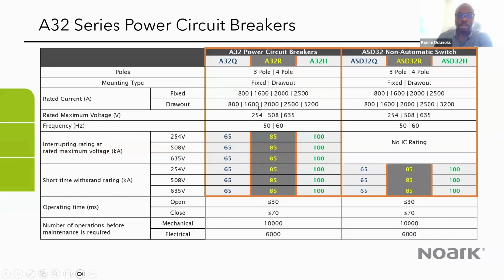Now to the specific specifications of the air circuit breakers. On my left here, we have the A32 power circuit breaker, and then you have the non-automatic switch, which is also known as a disconnect switch. So basically, you want the breaker to act like a switch, so it's not offering any protection. If you look at both families, we have 3 and 4 poles available. You can have both the fixed and the draw out mounting in both the power circuit breaker and the disconnect switches.